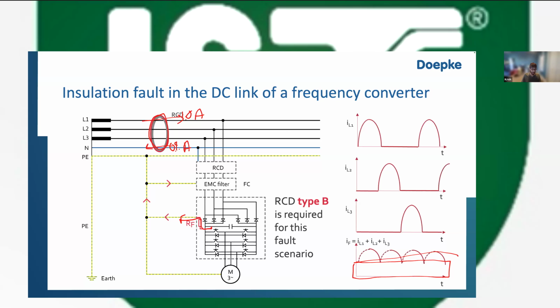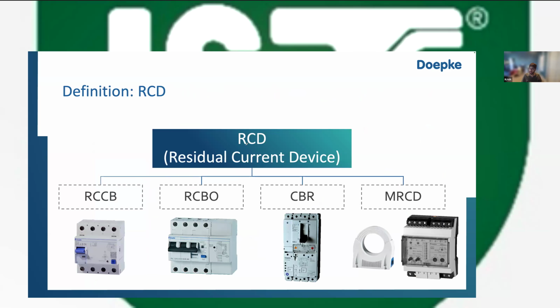The first thing I want to talk about is this ELCB versus RCD business. In the market, we only have available RCDs, which are either RCCBs, RCBOs, CBRs, and MRCDs. Colloquially, people call this device an ELCB. An ELCB is actually an earth leakage circuit breaker. It's no longer available in the market. It has a completely different operating principle. But in this case, most times when people refer to ELCB, they mean this RCCB device. When it comes to the rating, 300 milliampere may be correct, may not be correct. It depends on two things.